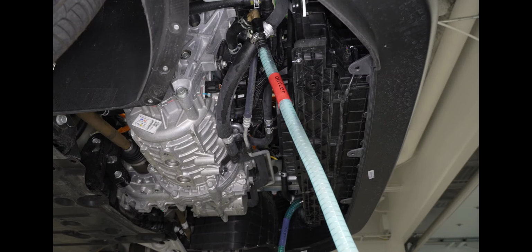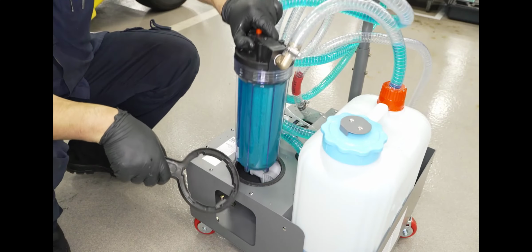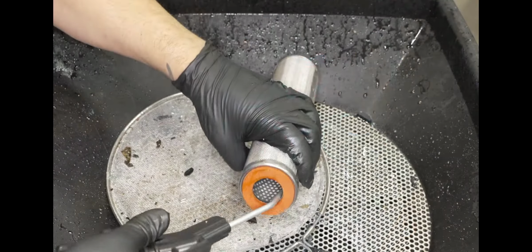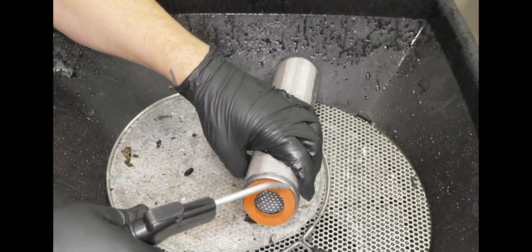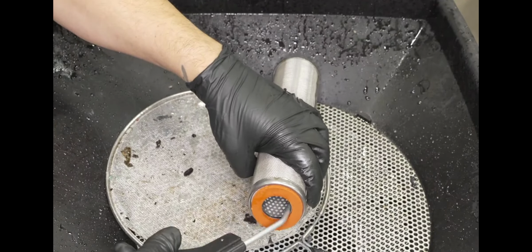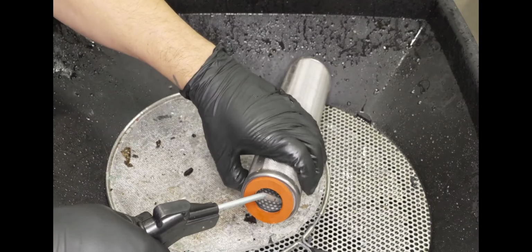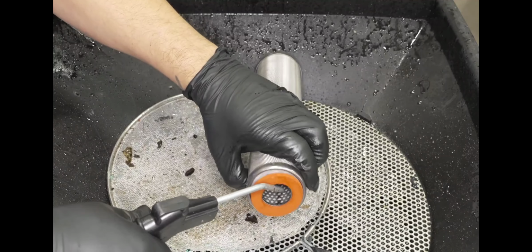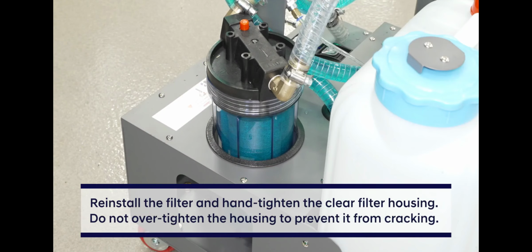After each cleaning job, it is necessary to clean the filter to ensure the tool performance for flushing and cleaning. Remove the filter from the coolant flushing equipment and use shop air to remove any debris from the filter or filter housing. Blow air from the inside of the filter outwards while rotating the filter. Reinstall the filter and hand tighten the clear filter housing. Do not over-tighten the housing to prevent it from cracking.